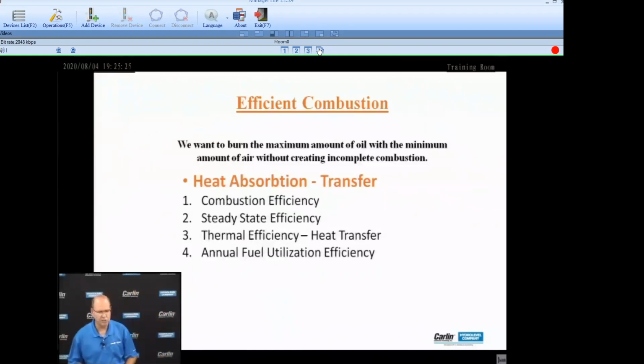Combustion efficiency, steady state efficiency. There's still a few people who don't understand the difference. The AFUE number that's written on your boiler is not the combustion efficiency number that you demonstrate to your customer. That's not necessarily the number that the customer is asking you to achieve. You need to be able to explain the difference between the two, possibly even understand why these numbers don't match up. Steady state efficiency. So how many guys will leave behind a printout for the customer that shows a high combustion efficiency number, yet when you look at the flue gas temperature, it was probably taken early on in the heat cycle, and flue gas temperature is running somewhere around 300 degrees, 310 degrees. That's probably cold water or cold air running through the appliance, and you haven't yet reached your steady state temperature.